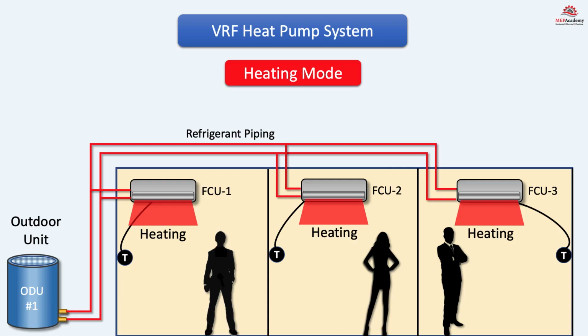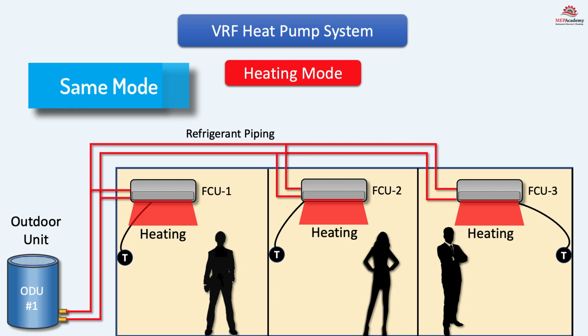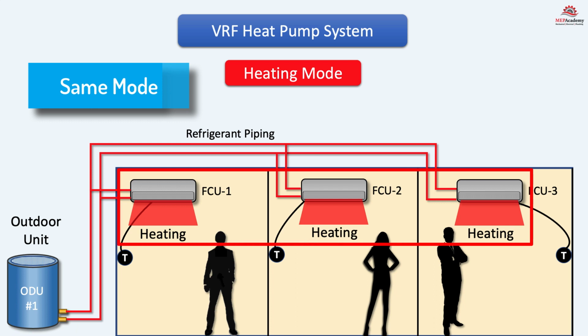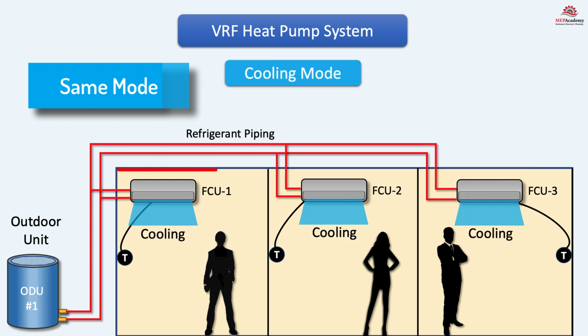One of the big differences between a VRF heat pump and heat recovery system is that with a VRF heat pump system, all the units must be in the same mode, either cooling or heating. As seen here, this one outdoor unit can feed many indoor units, but all the indoor units need to be in the same mode, such as heating as shown here, or all in cooling.